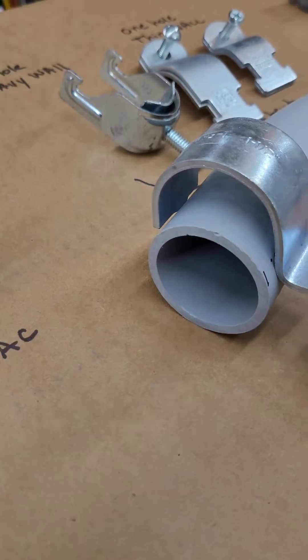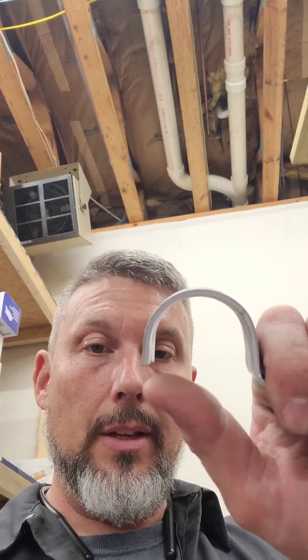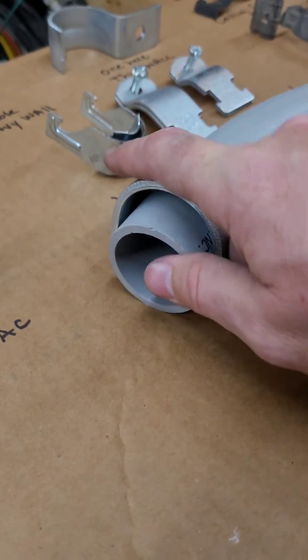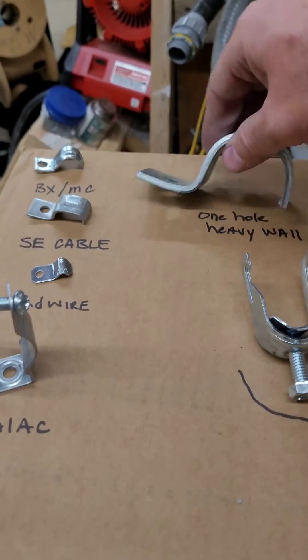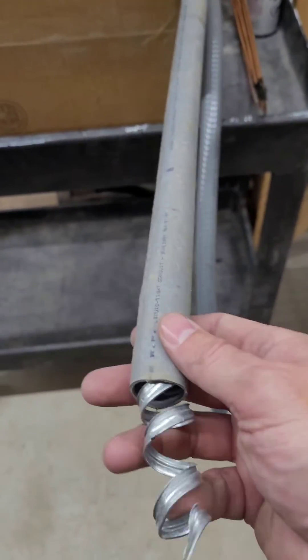The thin wall won't fit it. Now, if you run across the occasion that you have to use a thin wall strap, you can just take it and widen it out a little bit and it'll go over it and work for what you're trying to do. But if you have it available, just use the heavy wall. The heavy wall will also be good for your liquid-tight non-metallic, Carflex, and also your Sealtite or metallic.